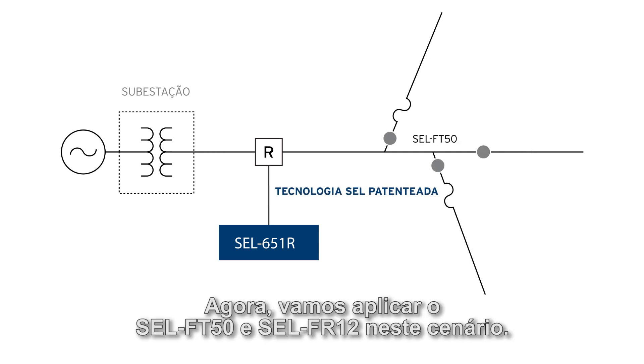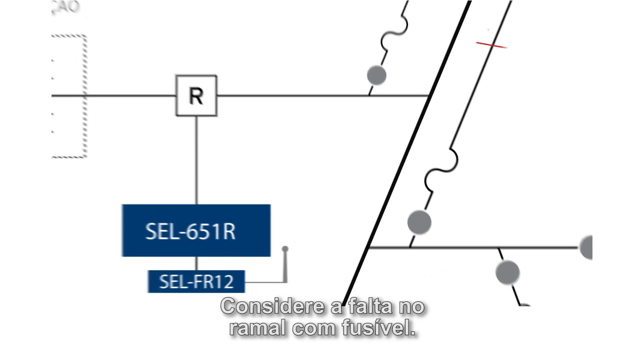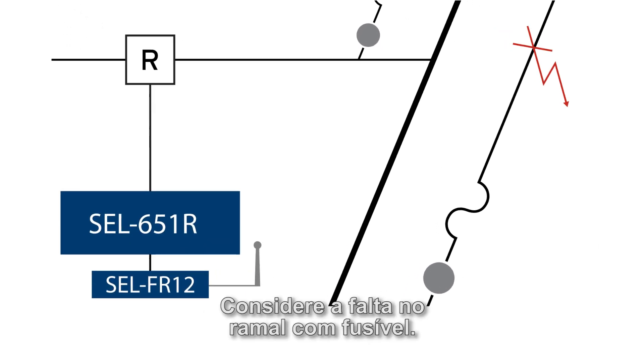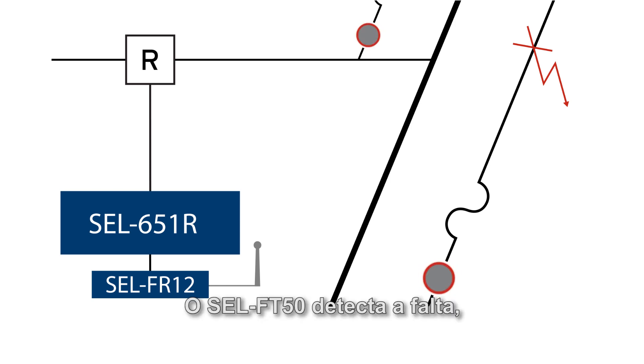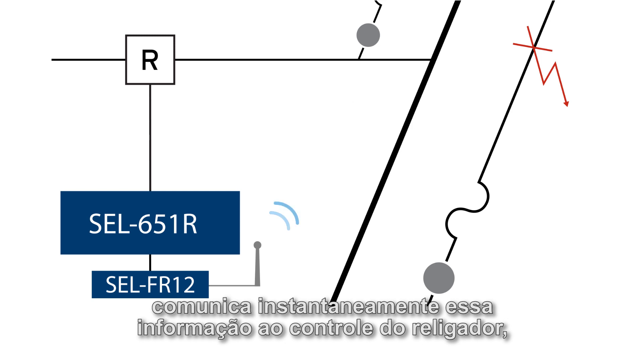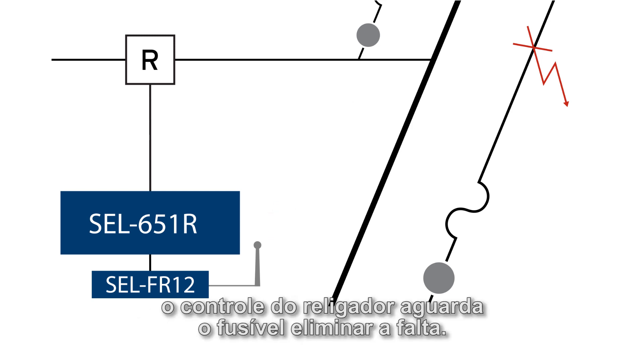Now let's apply the FT50 and FR12 to this scenario. Consider the fault on this fused line. The FT50 detects the fault instantaneously and communicates that information to the recloser control. The recloser control waits for the fuse to clear the fault.